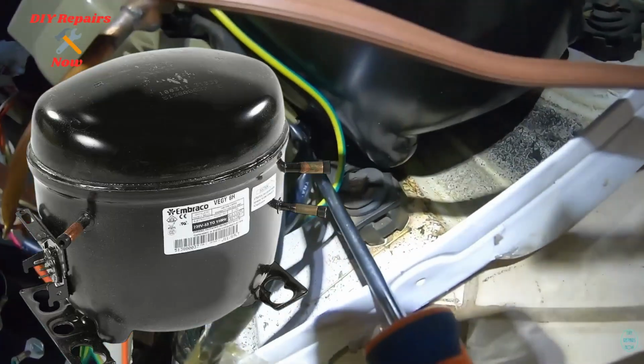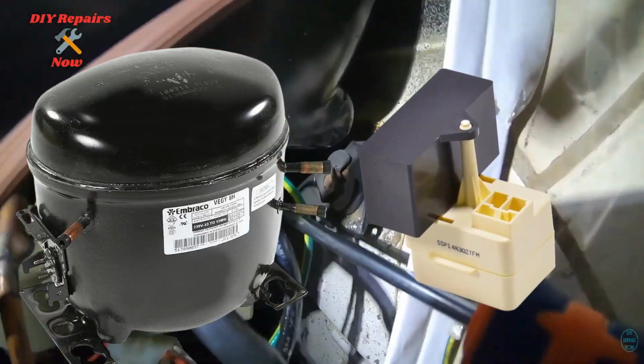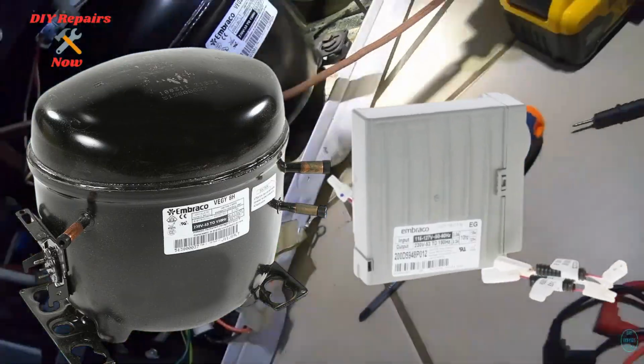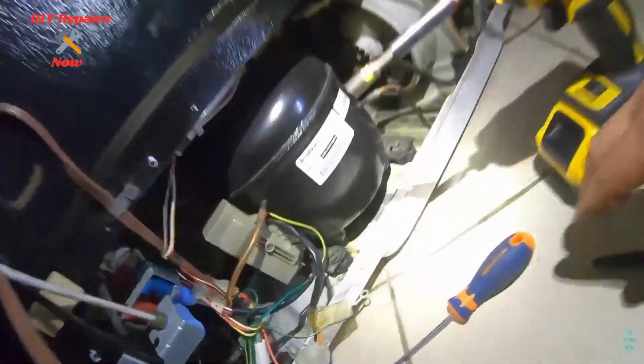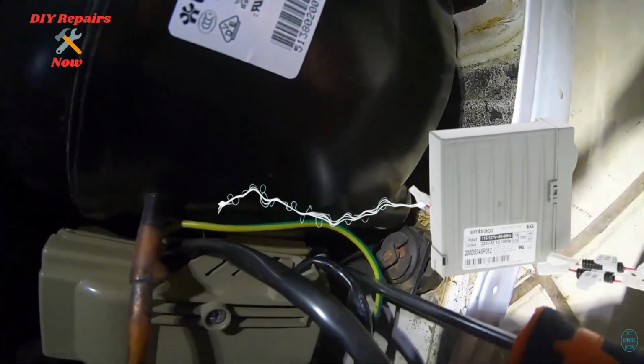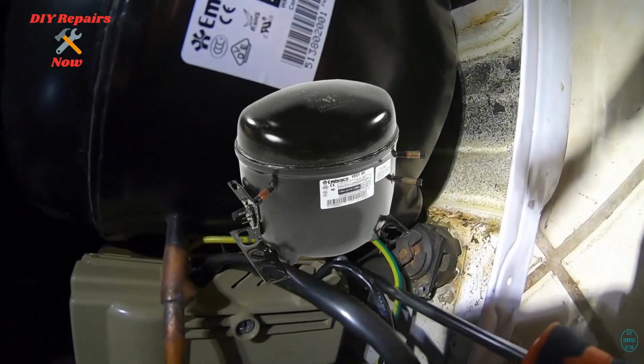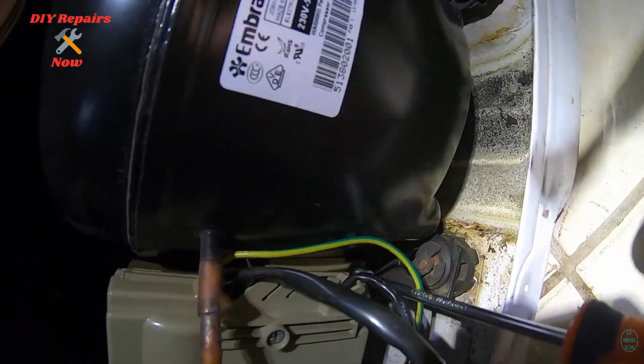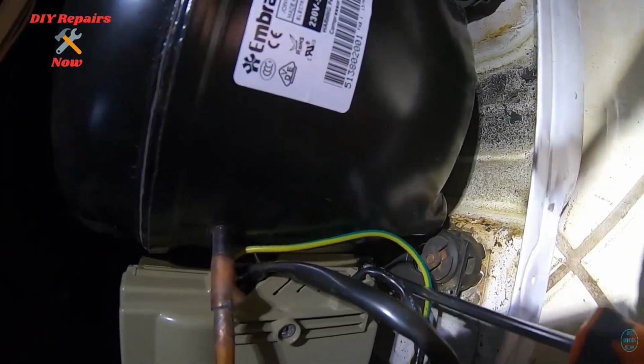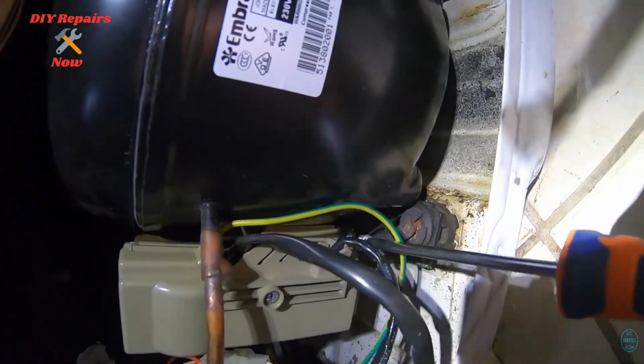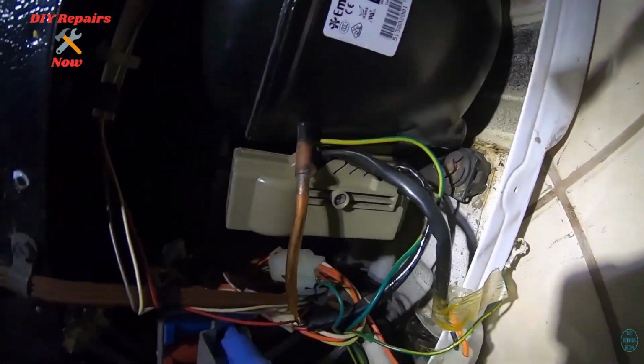Unlike a traditional refrigerator compressor that typically operates at a fixed speed, an inverter compressor can run at different speeds depending on how much cooling the refrigerator needs. The inverter board receives information from the refrigerator's control system and uses that information to control the compressor. You can usually find the inverter board mounted near the compressor, commonly at the bottom rear of the refrigerator. Depending on the manufacturer and model, the design and location can be different.